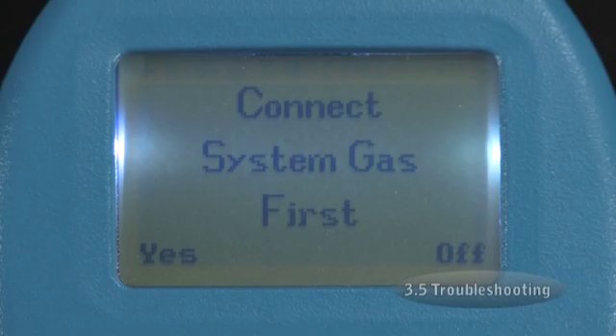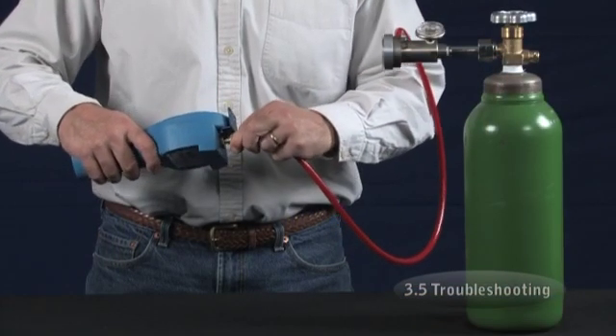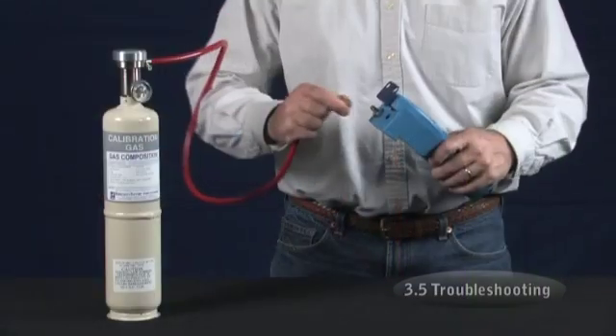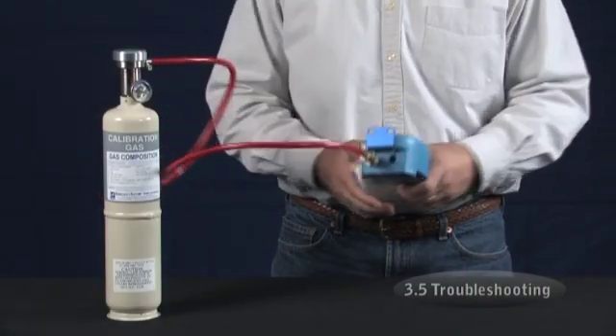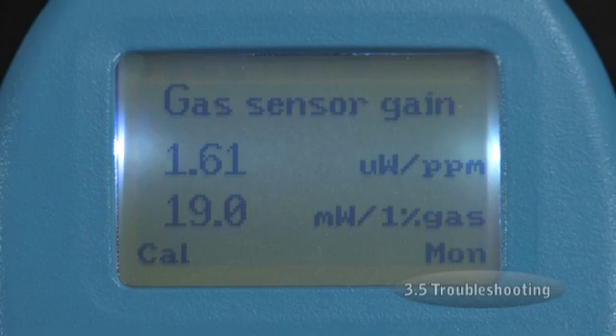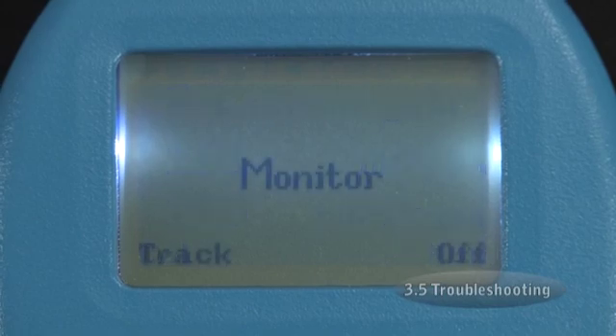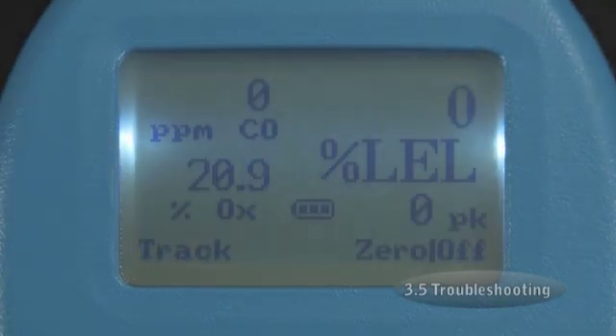Complete calibration as usual, first using 100% methane or system gas, and then Bascom-Turner cal gas. Once you have completed calibration with both gases, press the right button beneath the word MON to enter the monitor mode, or turn the Explorer off. This completes the new filament routine.